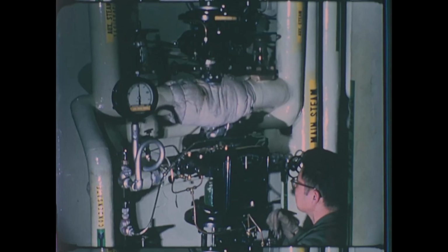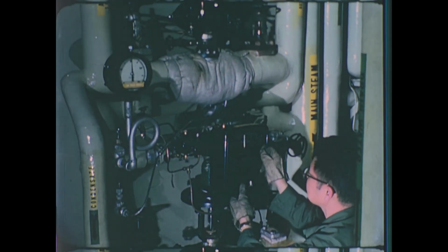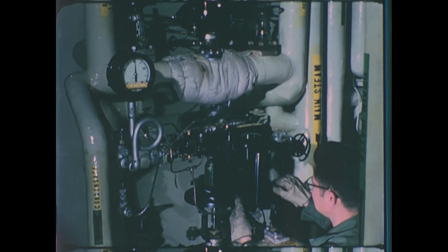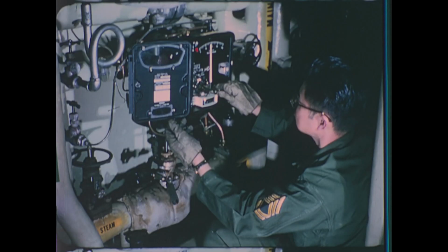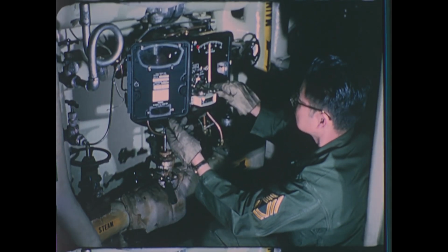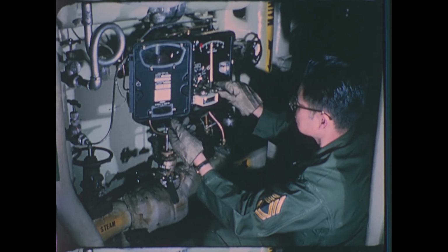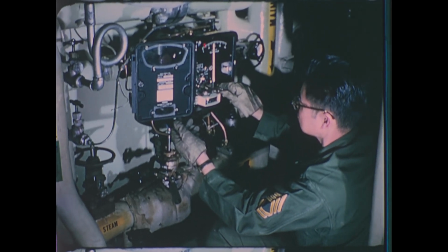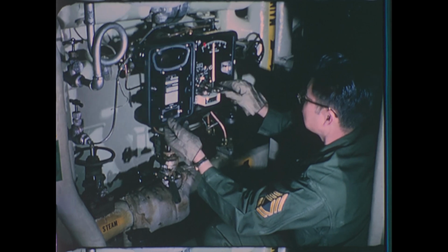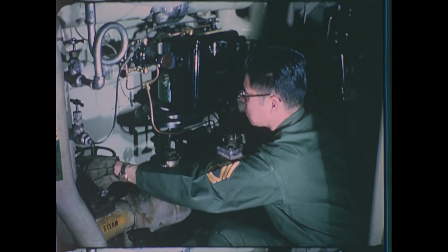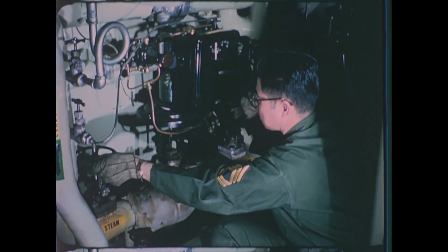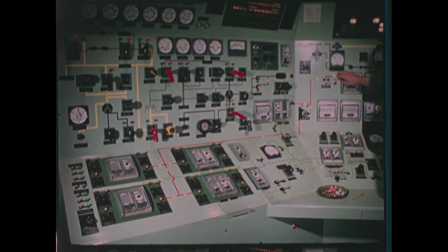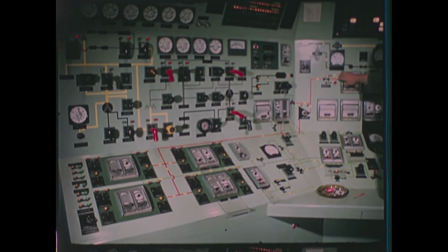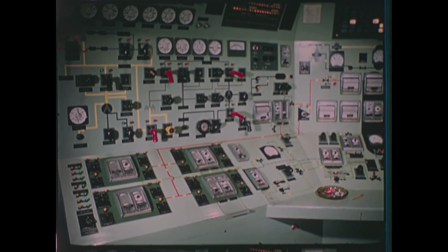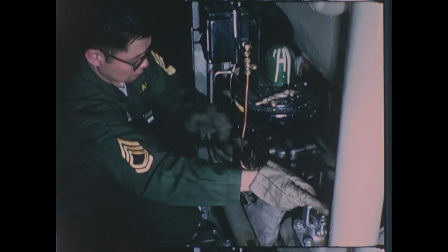He adjusts the auxiliary steam pressure regulator slowly, increasing the pressure to 110 pounds. The plant auxiliary system is now in operation, using steam from the primary plant steam generator. With steam pressure equalized across the main steam stop valve, the valve is opened remotely. Line up the deaerator pressure controller and line up steam trap.